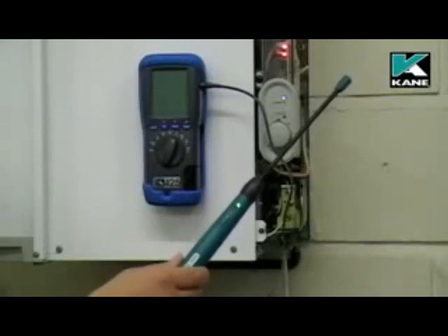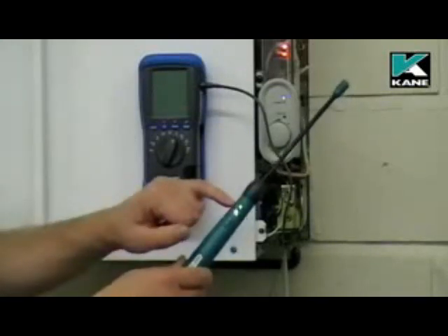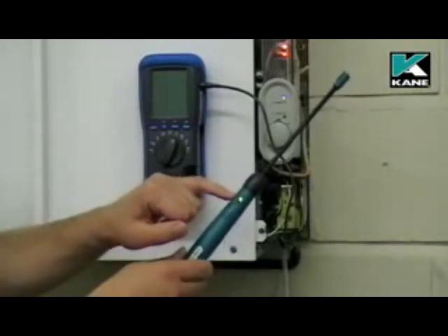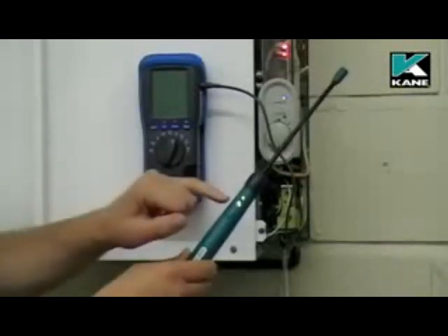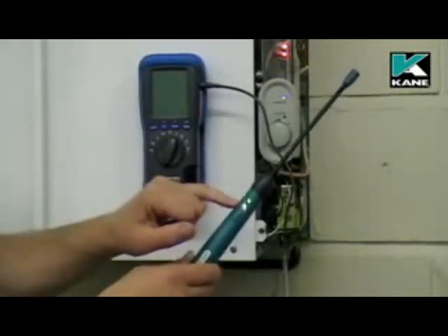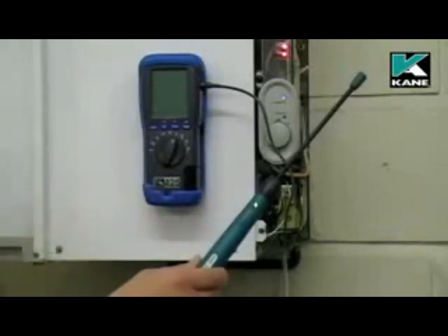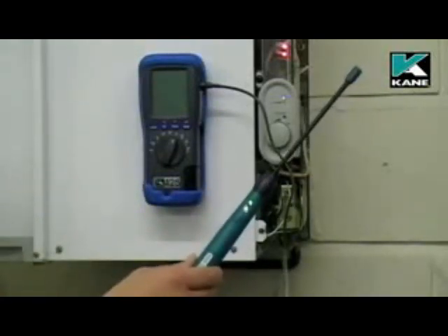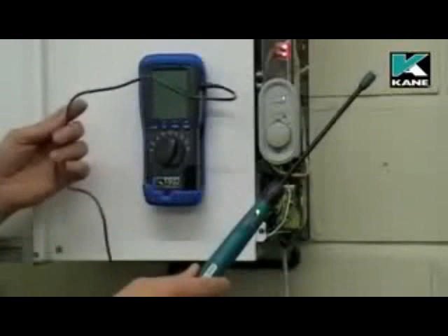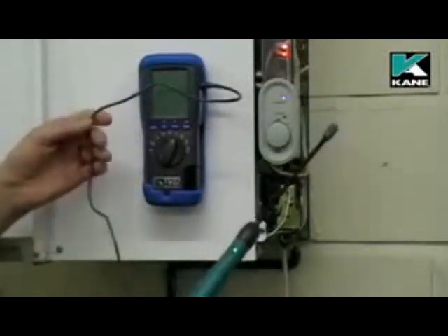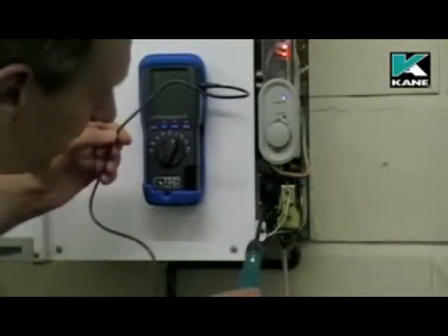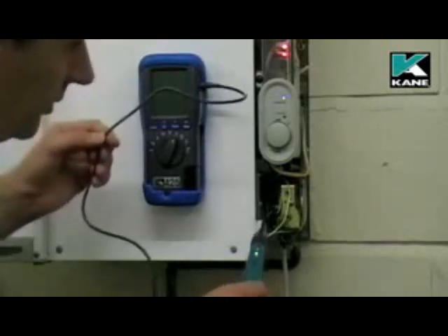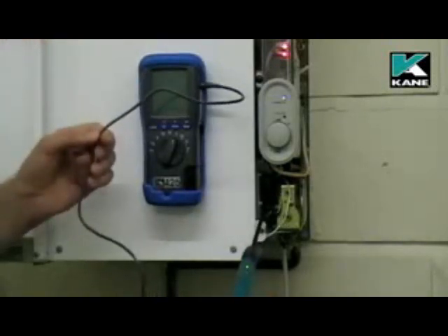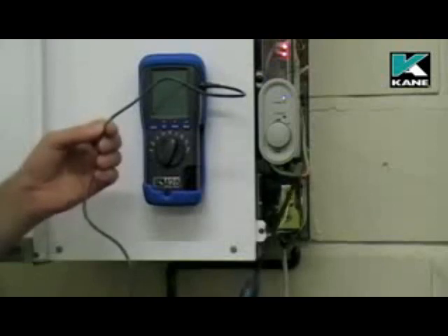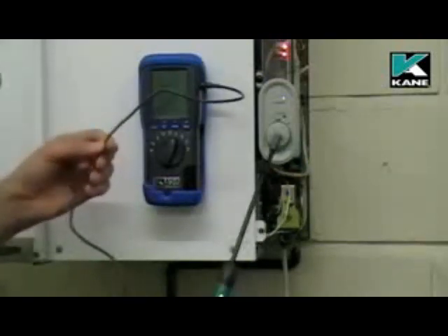When it's finished its calibration, the green light stays on, which means that the battery power is sufficient. The amber light pulses, and there's also an audible tick. If we now move the head of the gas leak detector to the test point, we can see there's no speeding up, therefore the test point is gas tight.